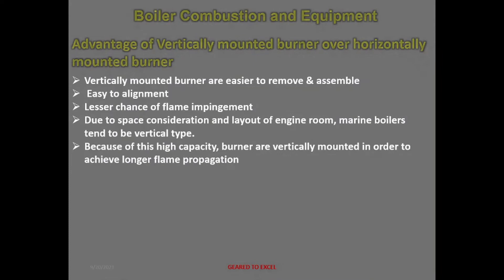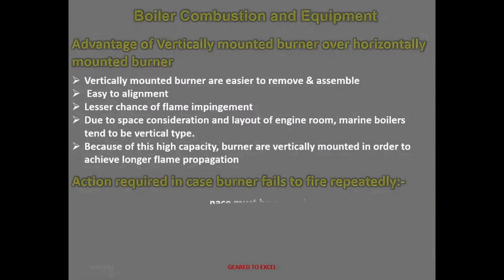Actions required when a burner fails to fire repeatedly: the furnace must be purged properly before each attempt. A maximum of two or three attempts should be made. After that, the burner should be shut down for thorough investigation. Check and rectify the exact problem before retrying. Do not attempt more than two to three times, as unburned oil will accumulate in the furnace bottom. The furnace must be checked for oil accumulation.